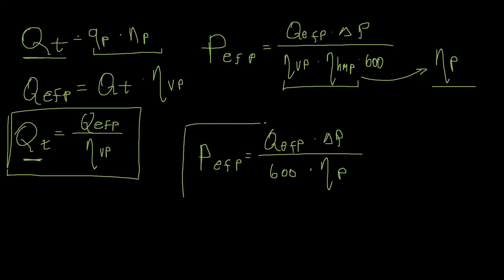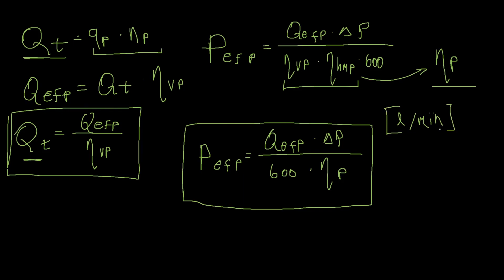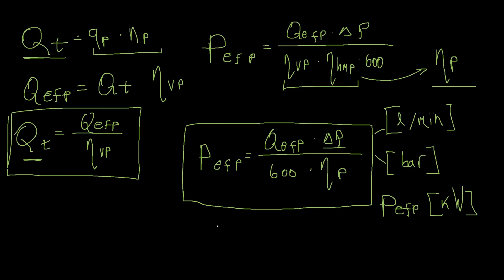In this equation, the flow rate is in liters per minute and the pressure is in bars. When you put these units into the equation, the effective power comes out in kilowatts. When we discussed axial piston pump sizing, I included a lesson from my second hydraulics course explaining efficiency factors — you should already know those concepts from there. If not, go back to the axial piston pump lesson and look in the resource section for the efficiency factors lesson.